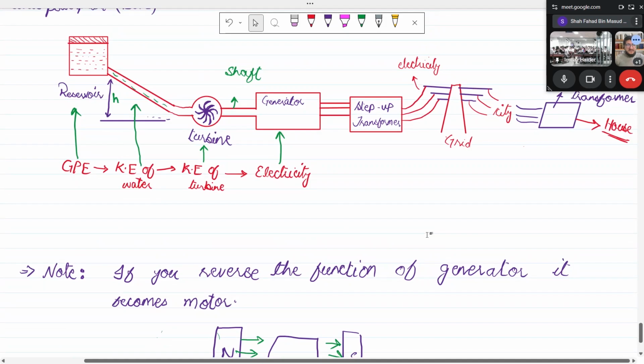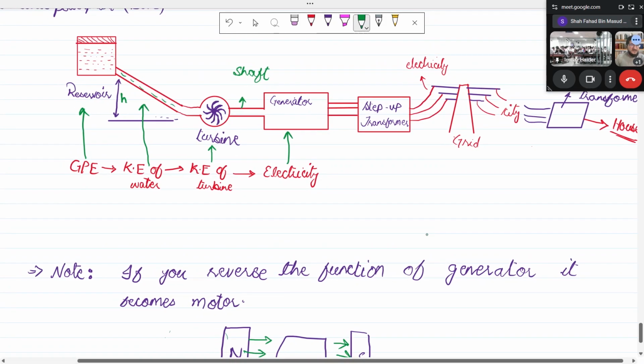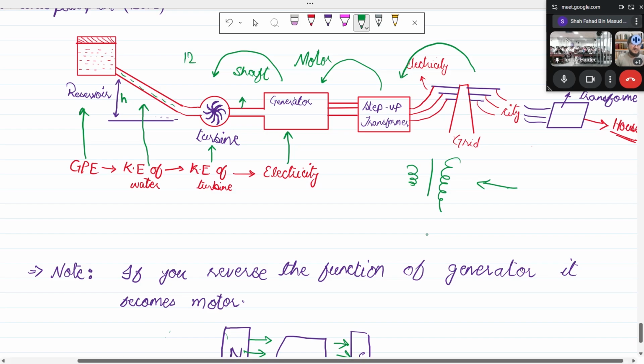अब मैं आपको इसमें समझाता हूँ. मेरा बच्चा हुआ ये कि हमारी जो करंट थी ना, वो मेन ग्रिड से ट्रांसफार्मर में आने लगी. ट्रांसफार्मर जो स्टेप अप ट्रांसफार्मर था वो स्टेप डाउन ट्रांसफार्मर बन गया फॉर अ माइनर सेकेंड्स. क्योंकि मैंने आपको क्या कहा था कि नाउ दिस इज योर प्राइमरी कॉइल एंड दिस आर योर सेकेंडरी कॉइल. अब जब करंट यहां से आ रही है तो प्राइमरी कॉइल ज्यादा, सेकेंडरी कॉइल कम है, तो स्टेप डाउन हो गया. और उसने स्टेप डाउन होके जनरेटर को मोटर बना दिया. और हमारी मोटर रन करने लगी, and within 2 seconds our RPM was approximately 120%. हम 120% पे पहुंच गए थे and it was a time when our whole plant was shaking.